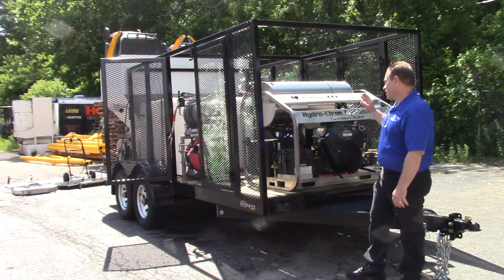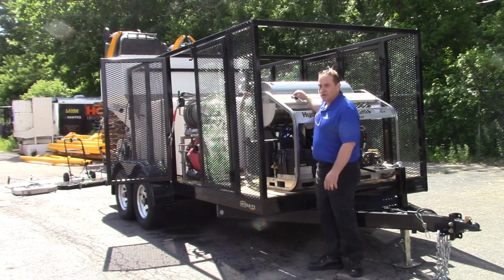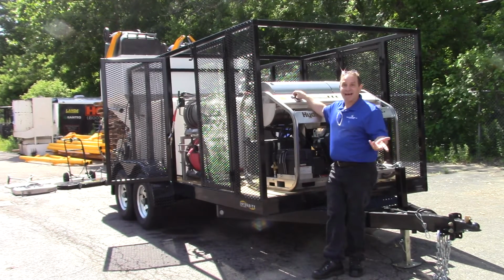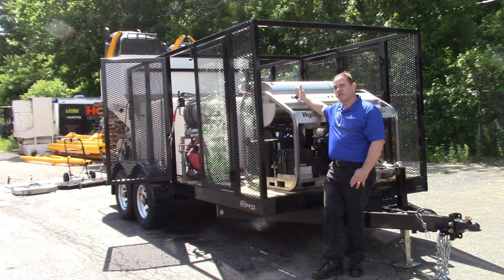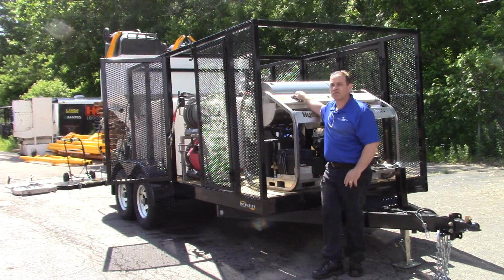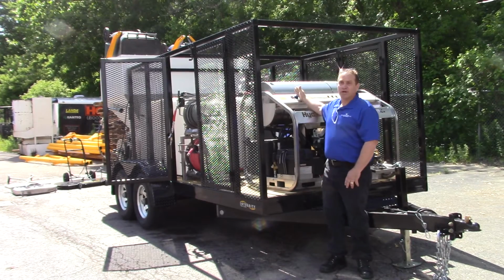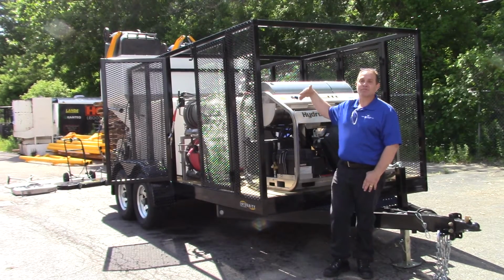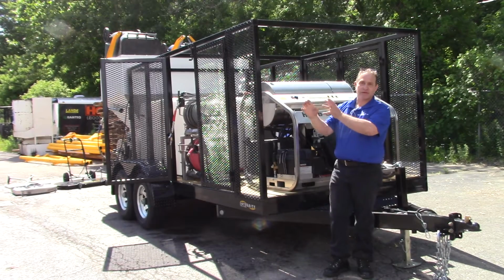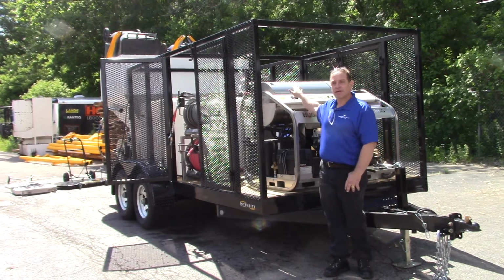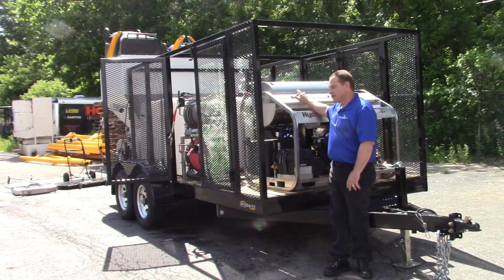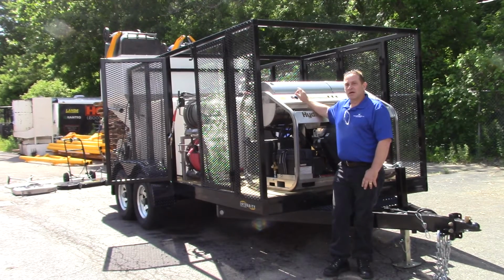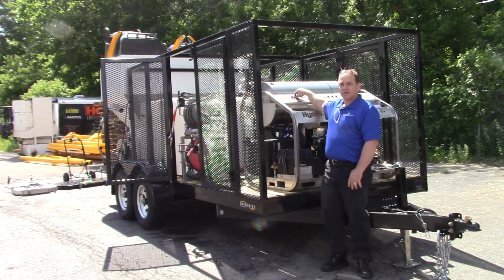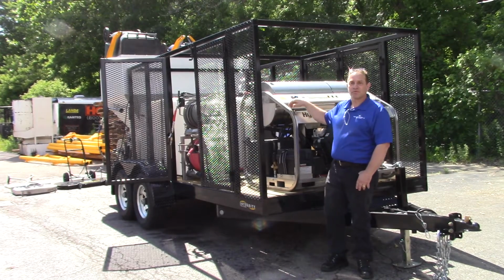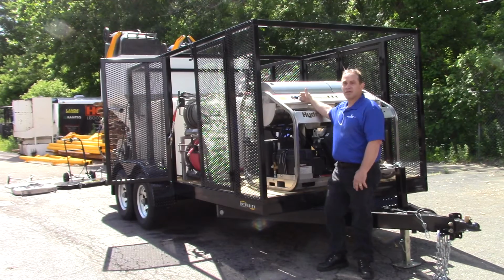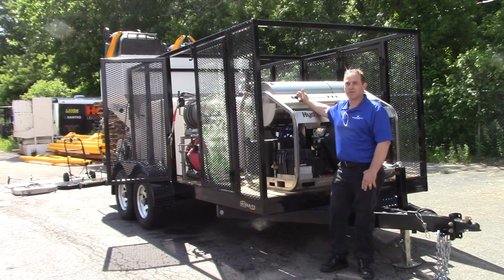What they have for those redundant safety devices, first one is the thermostat, which is also known as a high limit switch. It's designed to really run up to 200, 225 degrees or whatever it may be, rated for up to 250. And that is one safety device in itself, being a high limit switch. On that, or some are just a fixed temperature that kicks on and off the burner and it's non-adjustable. So your thermostat in this case normally runs and shuts down the fuel solenoid. So say something went wrong and then the redundant safety devices started kicking in, this is eliminating your fuel to the burner assembly, the diesel fuel.